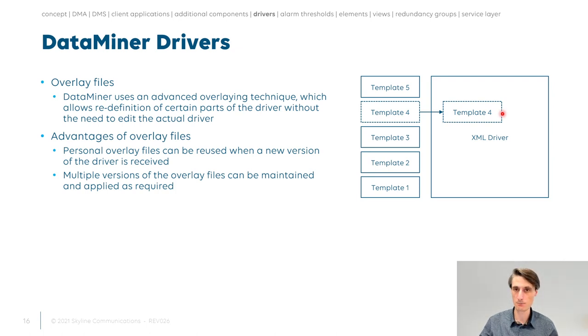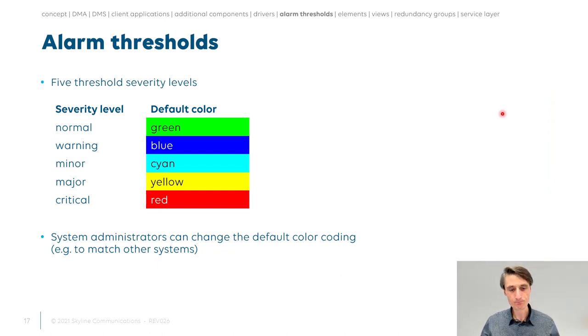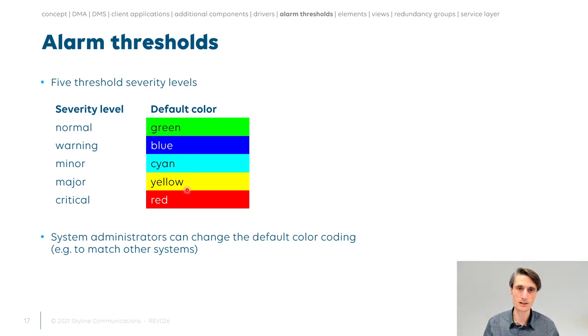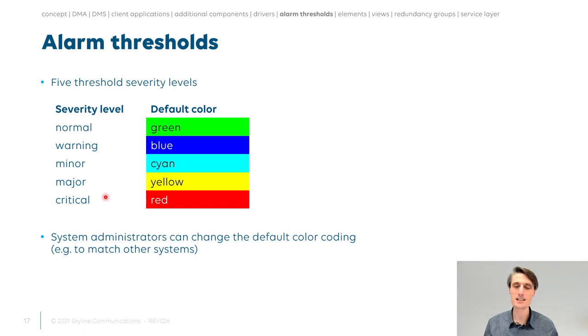When data is in the DataMiner system and hosted in elements, it can generate alarms. The alarm levels available are: normal (no alarm), warning, minor, major, and critical. The default colors are blue, cyan, yellow, and red. Note that the administrator can change these colors in a config file. You don't have to use all levels — if you're not interested in minor alarms, simply don't configure any thresholds for that level.